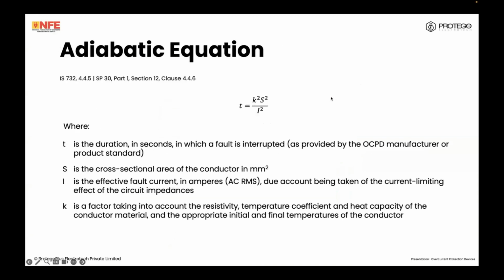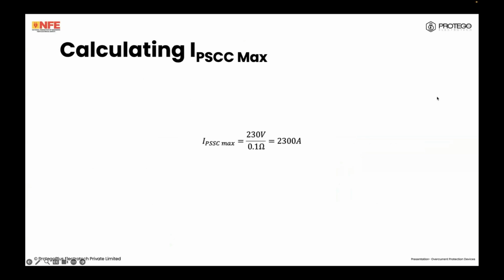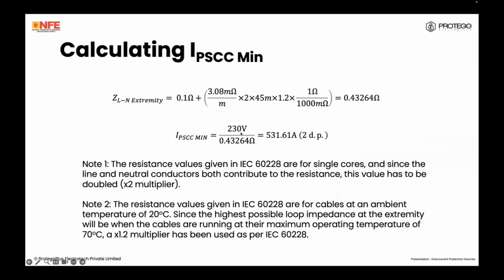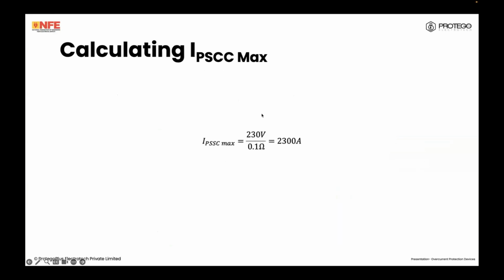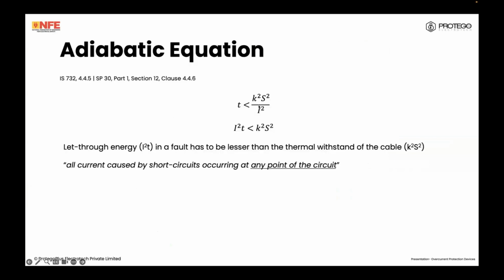Now, given the short circuit loop impedance, the line to neutral loop impedance at the end, we do 230 divided by this value and we get 531.61 amps. Let's just call it 530. It's a minimum, so we'll round it to 530. So now we have our I values at the beginning and at the end. S is known. How do we get K?